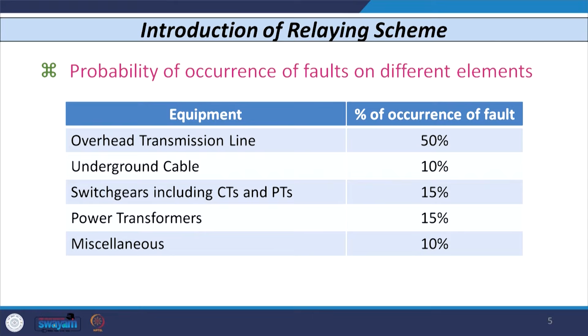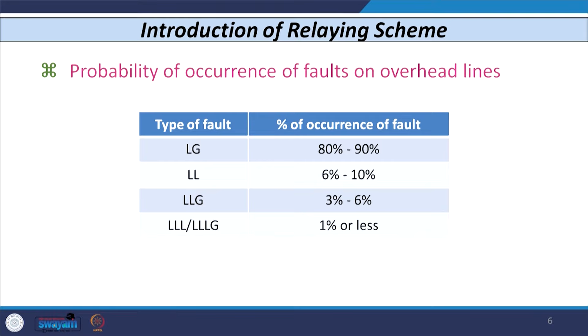Also, let us consider the probability of occurrence of faults on overhead lines. Depending upon the type of fault, the percentage of occurrence also changes. If I consider single line to ground fault, then 80 to 90% are the chances for occurrence of this type of fault on overhead conductors. For line to line fault, 6 to 10% are the chances, and for double line to ground fault, 3 to 6%. For triple line or triple line to ground fault, which is a symmetrical fault, the chances are very rare, 1% or even lower than that. So, from this table we can conclude that the single line to ground fault is the most common type of fault that occurs on overhead conductors.